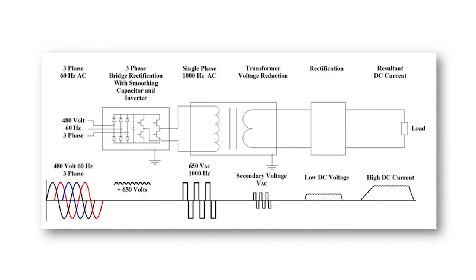So on the left side of the screen, you can see that we have a 3-phase input that goes into our rectifier, goes to a DC bus, which is rectified at the peak of our voltage input. So in the case of 480 volts, that is approximately 678 volts at the peak. With some losses, we estimate a conservative 650 volts, which is then inverted using our MOSFETs switching at 1000 Hertz to an AC wave shape that can then be put into an MFDC RoMan transformer, which is then output to a heating element to allow the resistance heating process to operate for the customer.